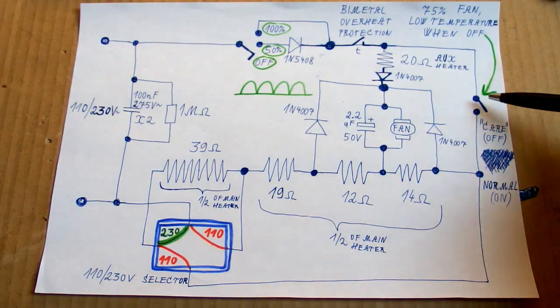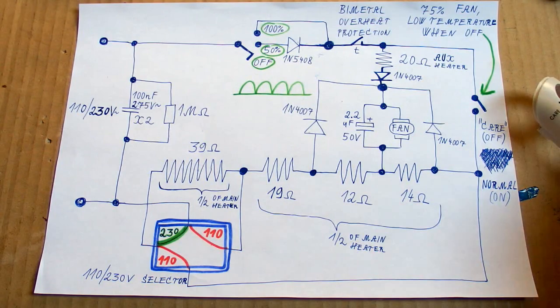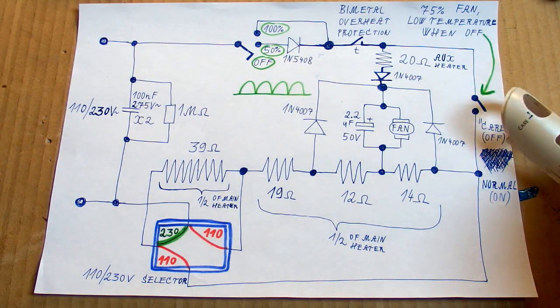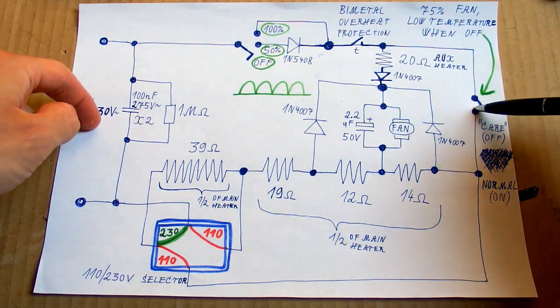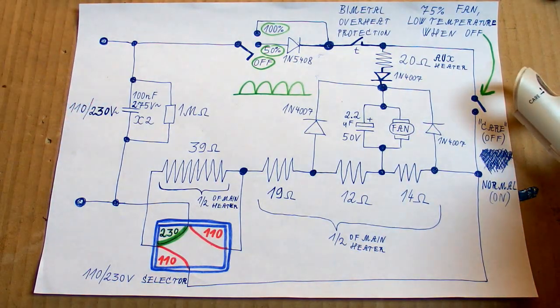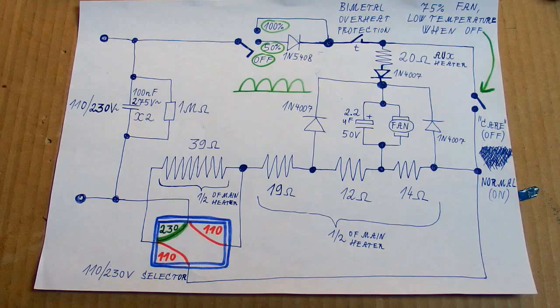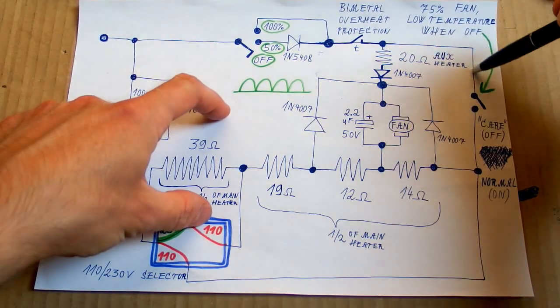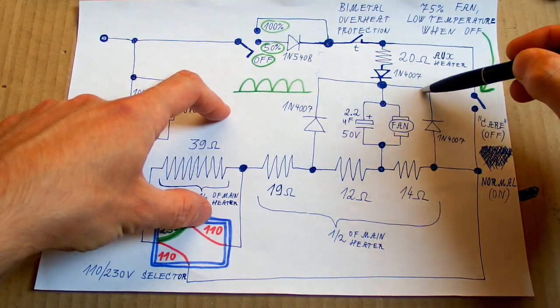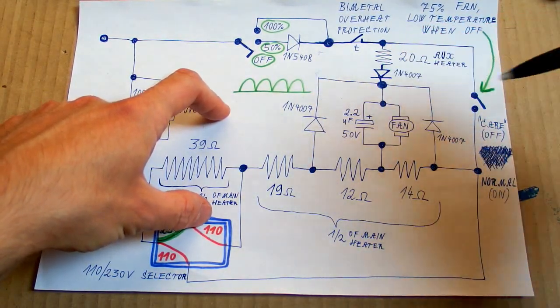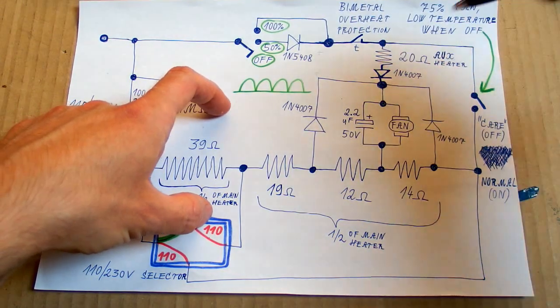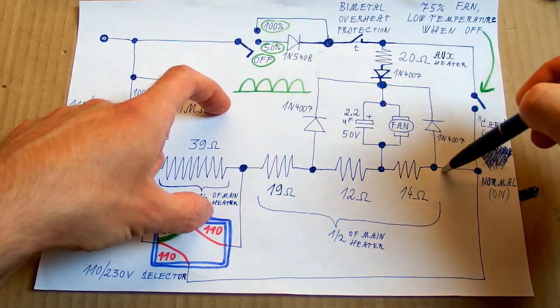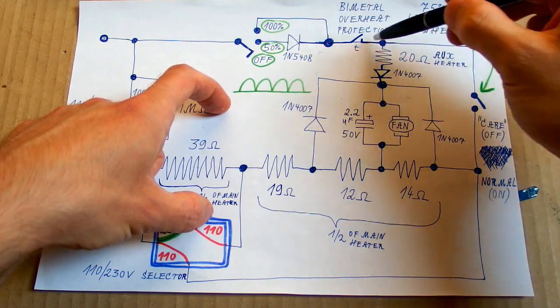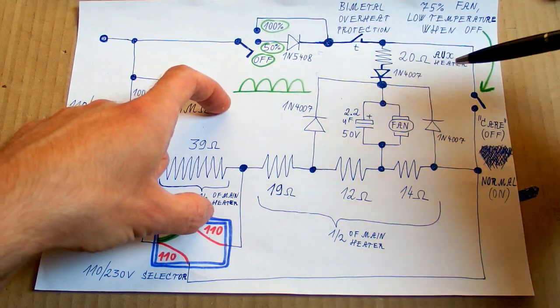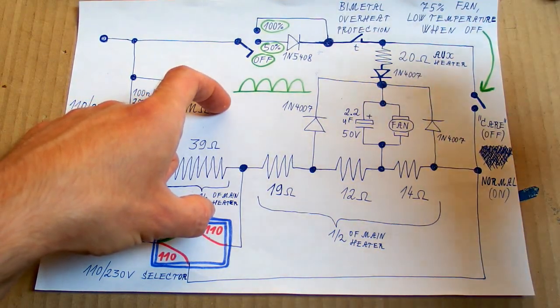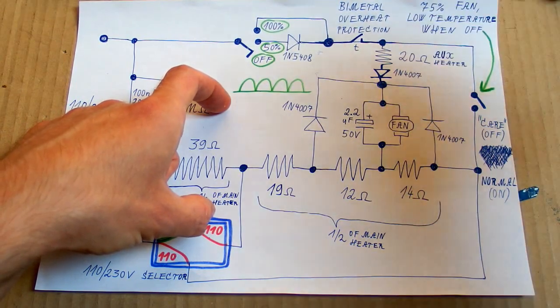Now there is this switch for a special function called care. In normal operation it's on, and when the care function is activated, it's off. In normal operation it's on, so the current goes into the motor via those diodes, and it doesn't have to go via this heater because it goes via the least resistance. Just via a diode and no heater, so in normal operation this heater has no current in it.